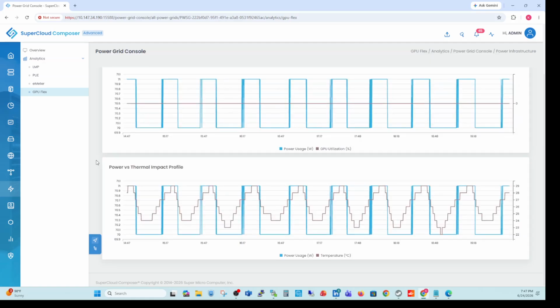And then the last piece is our GPU flex. We can flex GPUs based not only on pricing, but — differently here in Europe versus North America — based on curtailment: a signal sent from the curtailment service provider, such as a frequency response fluctuation, maybe an emergency where there's a blackout occurring, triggering a signal to curtail power. There are various use cases, and we set business rules to curtail based on that signal from the curtailment service provider. That service program exists in North America but not in Europe, because electricity is regulated in the European Union.